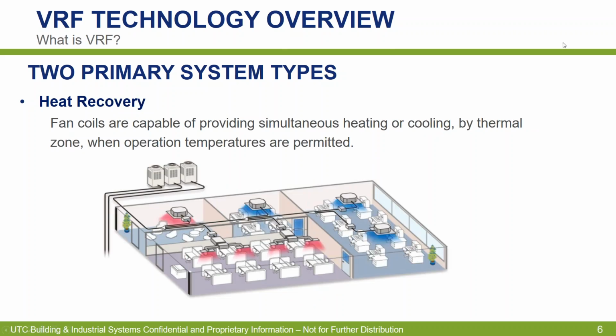Heat recovery. As you can see here, we have different shadings, right? So we have our blue, representative of cooling, and our red, representative of heating. Now this is more if your customer is looking for, and my analogy is, true 4-pipe control, right? Where you have both chilled water and hot water loops running around your building. You can essentially give your occupant cooling or heating 365, 24/7 or 24/4, whatever you want to call it. We've got it. Heat recovery is the best fit.